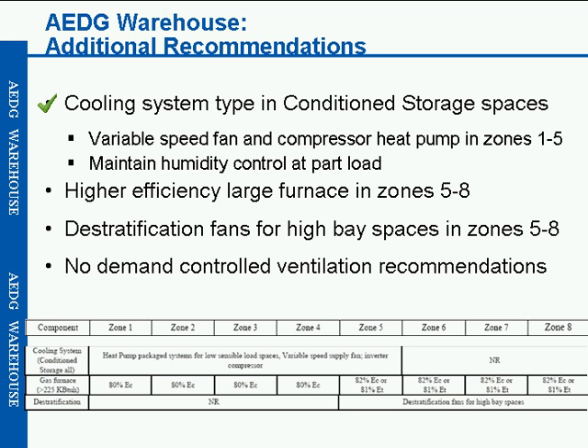Those additional recommendations include the cooling system type in the conditioned storage spaces, looking at variable speed fan and compressor heat pumps for zones 1 through 5, and maintaining humidity control at part load. It also requires a higher efficiency furnace in zones 5 through 8. One of the big differences in this guide is to use destratification fans in the high bay spaces, and there are specific how-to tips and explanations about those fans. There are also no demand-controlled ventilation recommendations in this section.